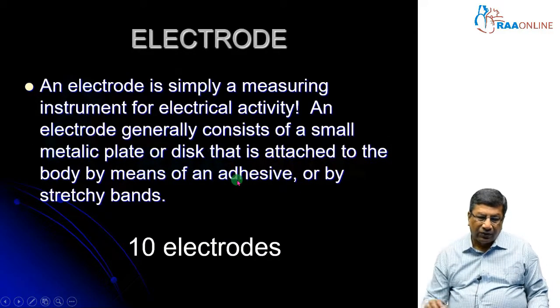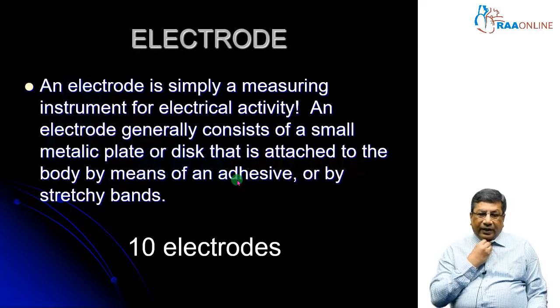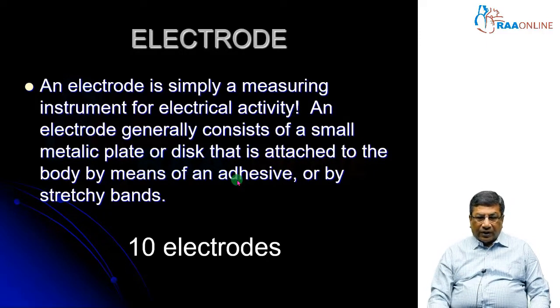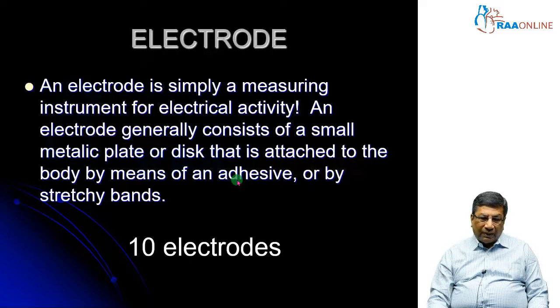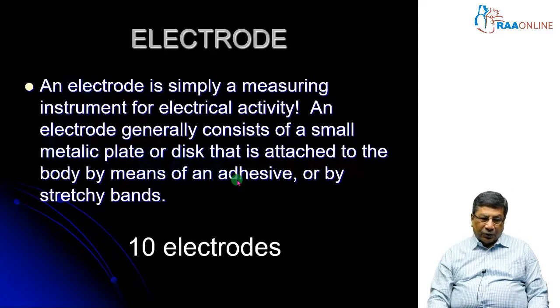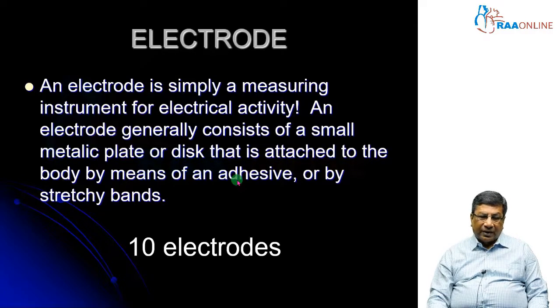Before we go into the leads, you must know the difference between an electrode and a lead. The electrode is a physical object — it is an electrical activity measuring instrument from the patient's body. It is usually a small metallic plate, a chest belt, or a disposable disc, attached to the body either by pasting the disc, putting the chest belt, or putting the metallic plate through stretchy bands on the limbs.